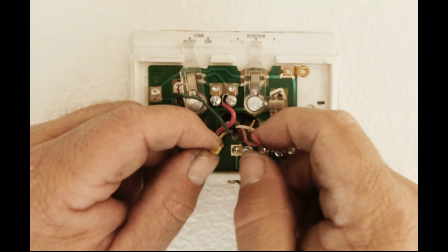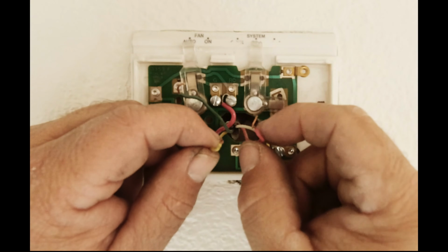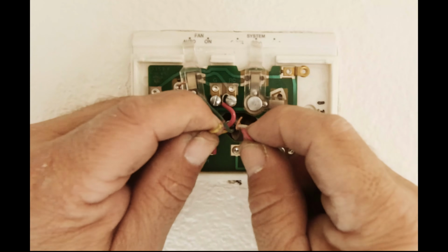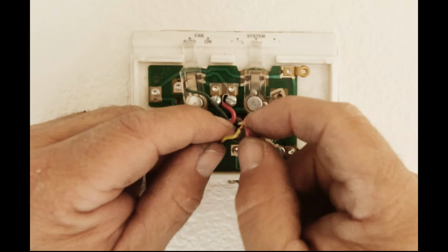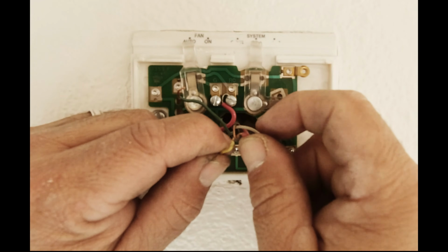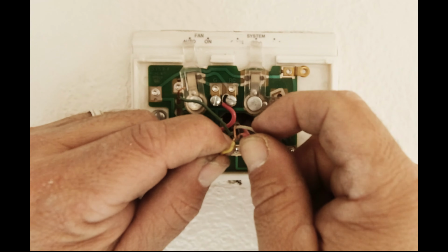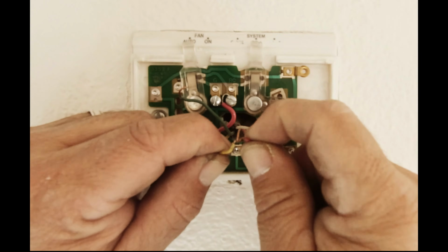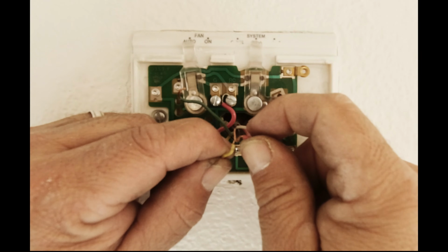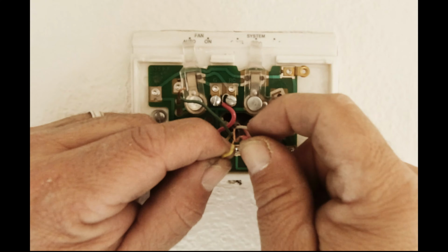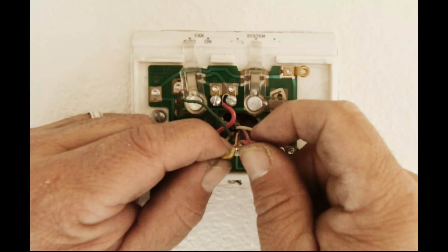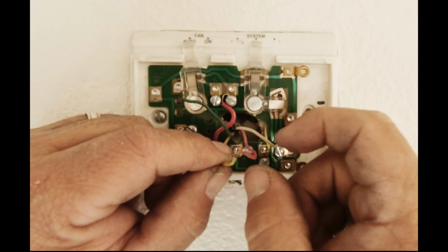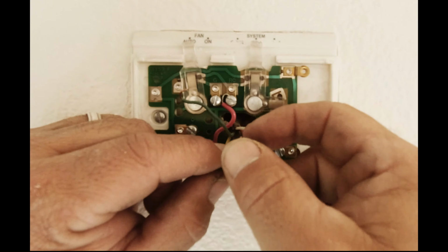So all you do is connect it. This is only 24 volts, so you'll be okay. If your hands are wet, you may get a tiny little shock, but you'll be all right. And then you should hear your compressor kick in. In this case, I didn't know that at the time when I did this video. It was not kicking in. That's why I'm trying it. I thought there was something wrong with the unit, but it was actually just at the breaker. Somebody had lowered the breaker.